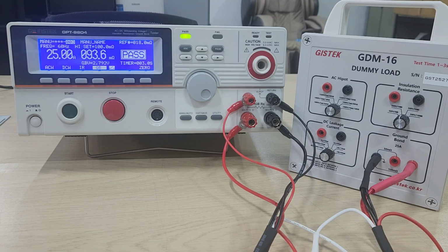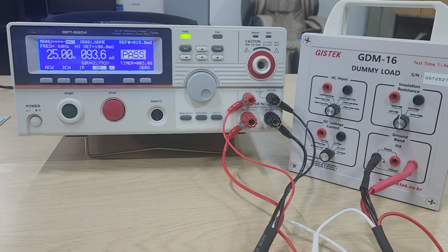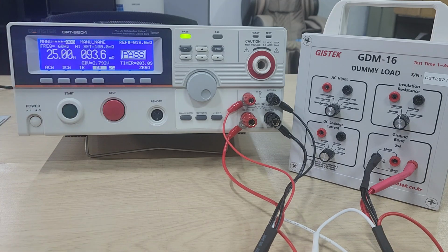And since the AC ground resistance test requires measuring a very low resistance value, approximately 100 milliohm, it is recommended to set the measured error value as an offset before use. Offset 18 milliohm.